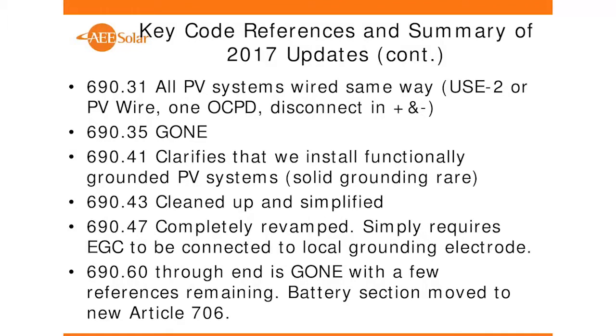Lovely. 690.60 through the end of the code of 690 is all gone, with a few references remaining. So we reference Article 705, we reference Article 706 for batteries, and we move all that stuff out of the code. So the good news, bad news is we removed about 3 pages of the 15 pages of Article 690. The bad news is that rapid shutdown brought back about a page. So, all right.